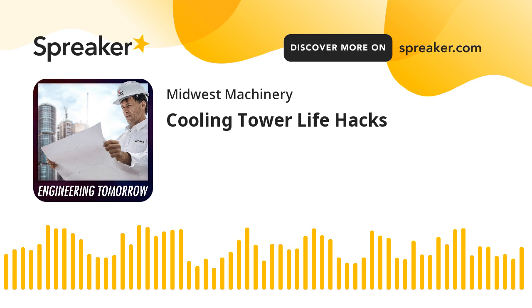Josh McCluskey asked, is there an advantage of one type of tower over the other for free cooling applications? I think the crossflow tower has significant advantages in cold water application. The challenge in counterflow towers is you have a plenum where the water is dropping some 3 to 4 feet, which can create a lot of splashing. When ambient conditions are low enough that we're using free cooling, we're trying to make 48, 49 degree water to go through a plate and frame heat exchanger to cool the process or building. So we already have very cold ambient conditions, and we're taking circulating water temperature down cold, right at the point of freezing to begin with. Then we start splashing it, the fans aren't running that much, and they tend to ice up a lot more than cross-flow towers.